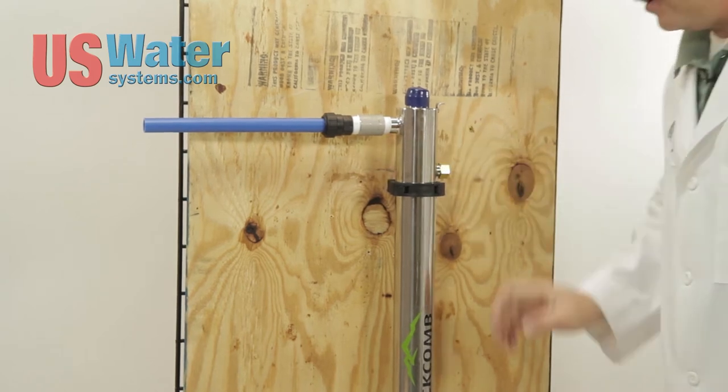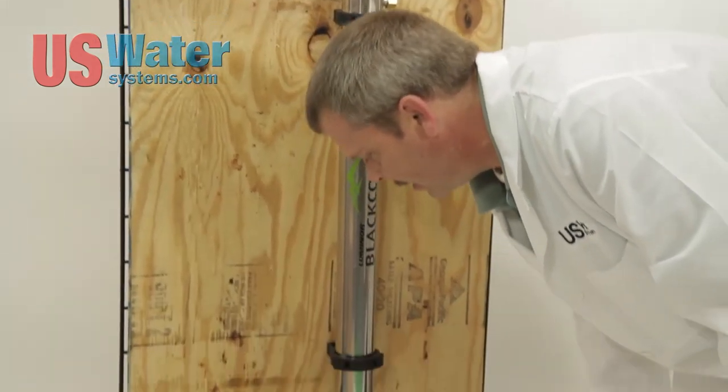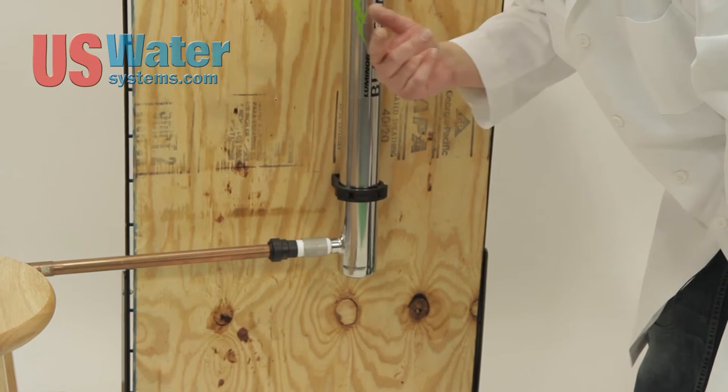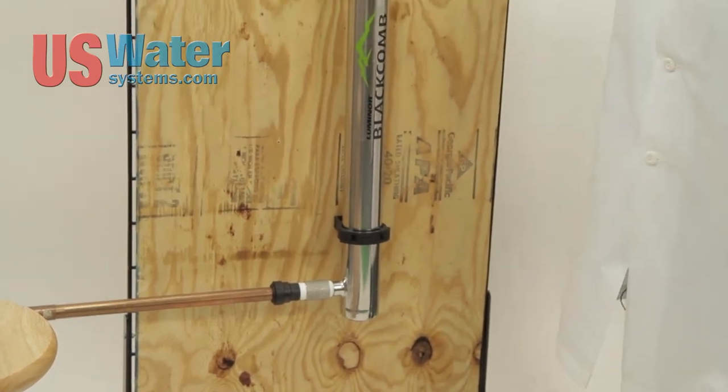In this particular situation we would bring this incoming pipe in from the bottom, elbow around, and then come into the system. This is a copper pipe which will fit right in this fitting. You can feel it hit the o-ring, push it on in the rest of the way. Once it's all the way in, then you tighten down the lock collar and now it can't come back out. This makes it really easy and fast to install. This is a PEX line and it works the same way. I'm just showing you the different types of line that you can use with these fittings.